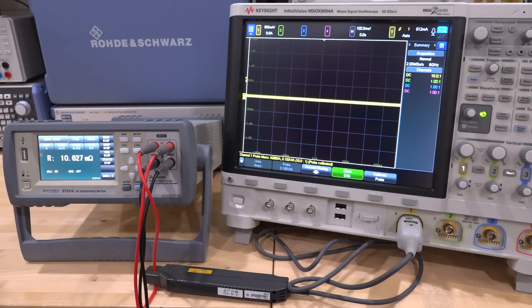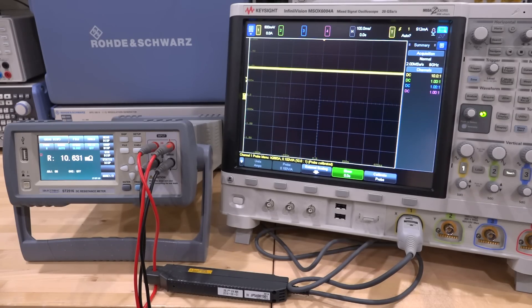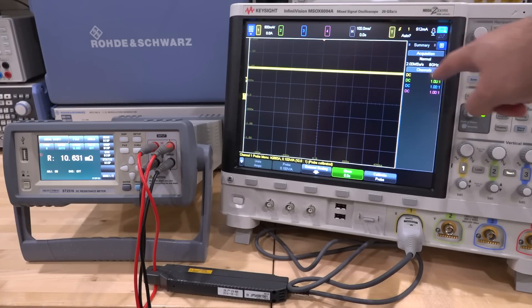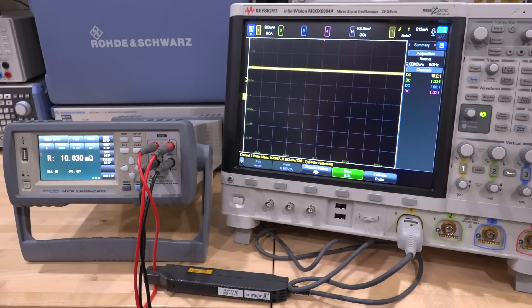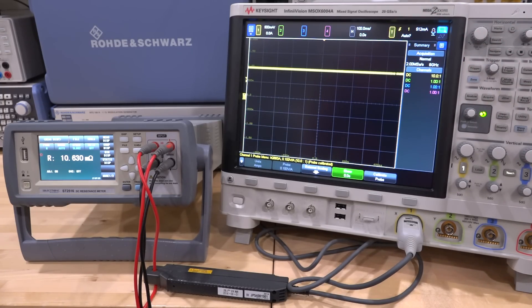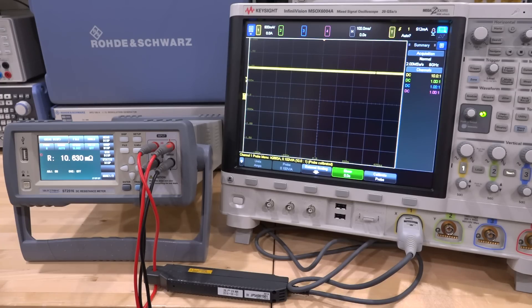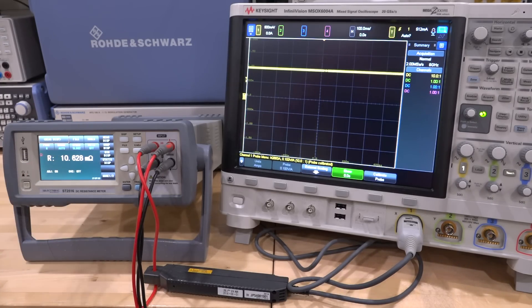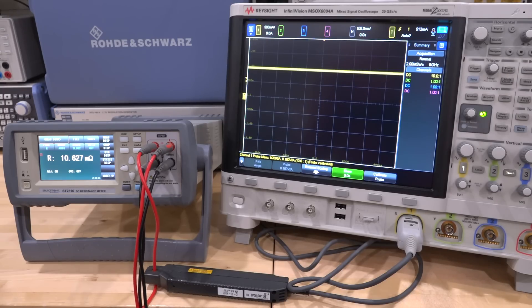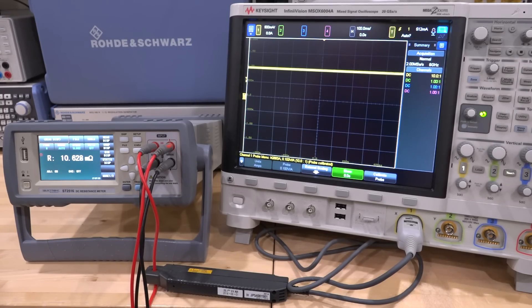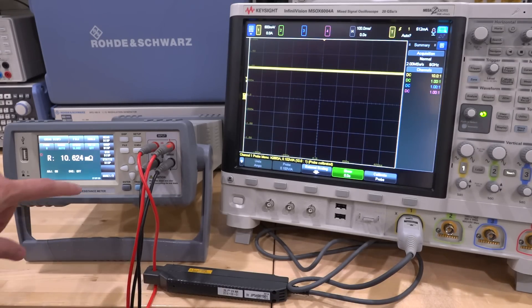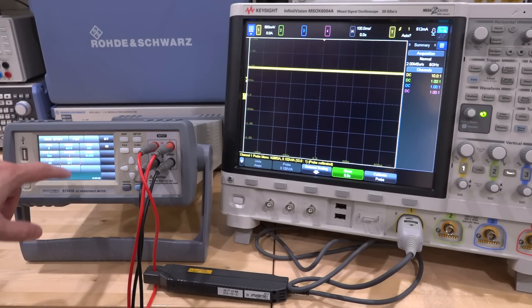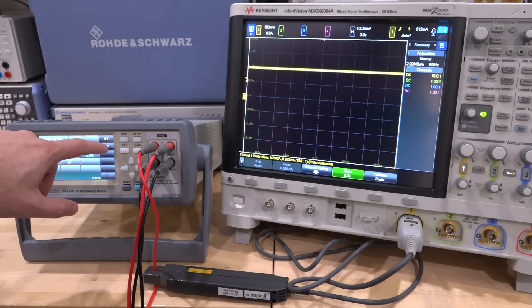We're going to measure our resistor here and we expect this instrument to push the entire one amp because this is a pretty small resistor and we'll let this settle and this is going to trigger. There it is, look at that, this is exactly one amp. So the instrument is doing exactly what we wanted to do, is pushing one amp of continuous current through the device under test and is measuring the voltage across it and that is going to give you from Ohm's law the measurement.